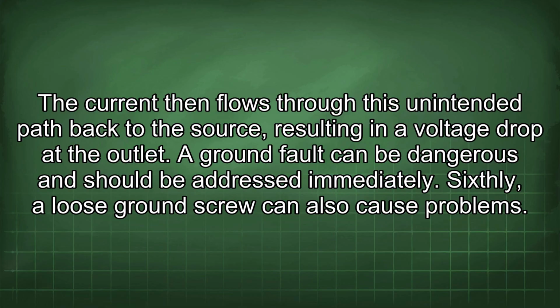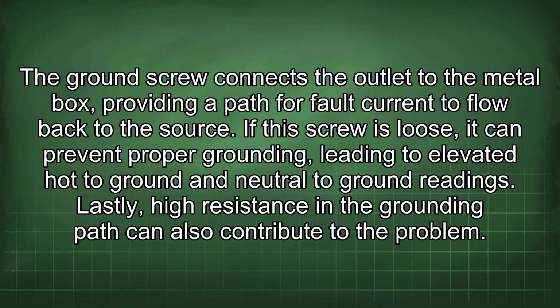Sixthly, a loose ground screw can also cause problems. The ground screw connects the outlet to the metal box, providing a path for fault current to flow back to the source. If this screw is loose, it can prevent proper grounding, leading to elevated hot to ground and neutral to ground readings. Lastly, high resistance in the grounding path can also contribute to the problem.